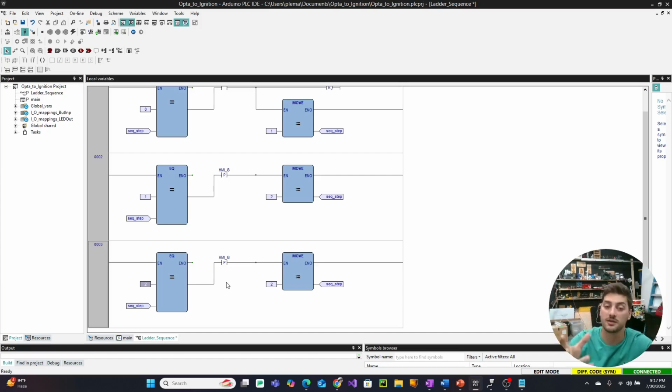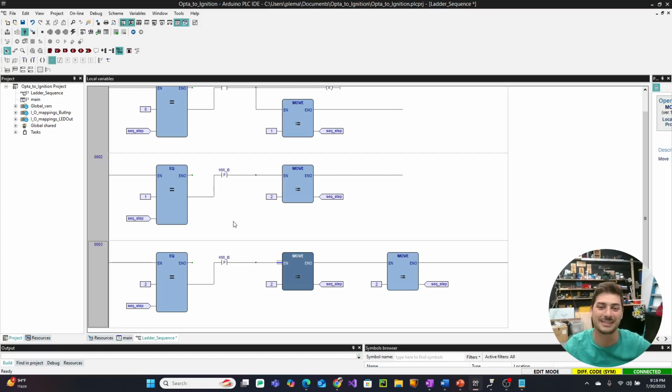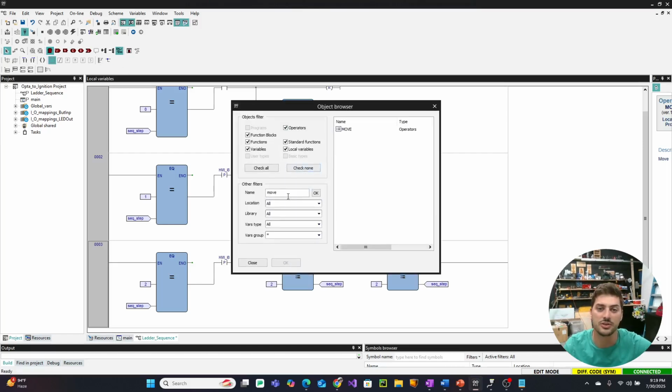Then there's a timer off delay, which is kind of the opposite, which is where when the conditions to start the timer begin, the output is immediately true, but then when the conditions that make the timer true go away, the timer will then start counting and stay true for a period of time after that. That's a lot of gobbledygook to try to explain what ought to be a simple concept, but with PLC programming, there is just a little game within the game of knowing the nuances going on here. So let's go ahead and drop a new block that we haven't seen before, but it's TON, timer on delay. And just to show you real quick, there's timer off delay.